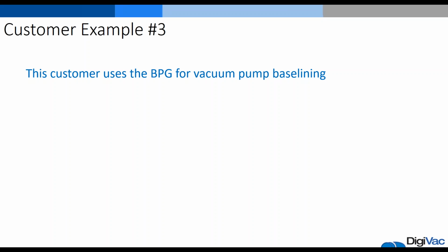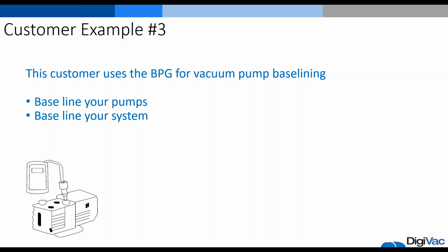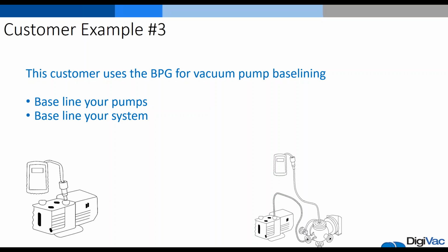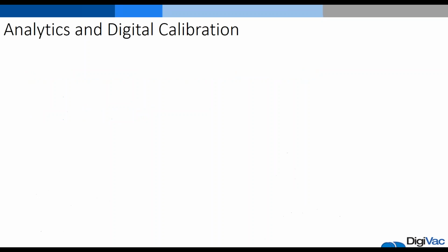Another customer example is a customer of ours that uses the BPG for vacuum pump baselining. So you can baseline your pump or you can baseline your vacuum system. To baseline your pump, you would plumb the sensor on the end of the Bullseye Precision Gauge directly into your pump to see what it's reading. And when you get a pressure, say 50 torr, you know that that's as low as the vacuum pump will go. And then you would plumb the gauge into the vacuum system itself to see what it's reading and make sure everything is accurate and lining up properly. If it's not, then you know there is an issue within your system that needs to be checked.